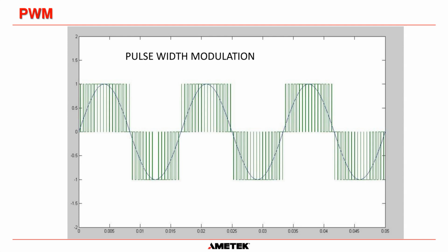Okay, the only thing that we are modulating or changing is the width of the pulse. So you can see this pulse here is extremely thin. It's just one line. But if you go into the center of the waveform, you can see that it's much thicker. It's actually that thick. And then we get out to this side here, and it's very, very thin again. So we have adjusted the width of the pulses. And the mathematical average of this pulse width modulated waveform is a sine wave. And basically we just put that through a transformer and capacitors, and it creates a near perfect sine wave on the output.